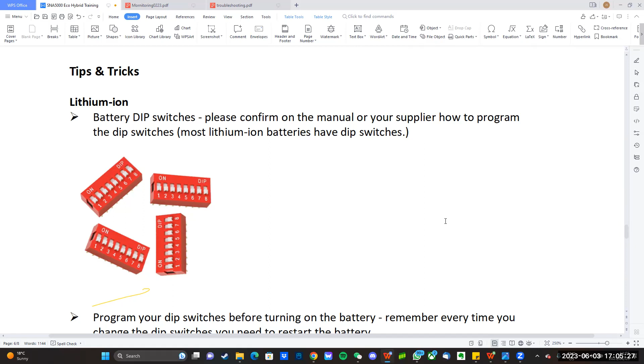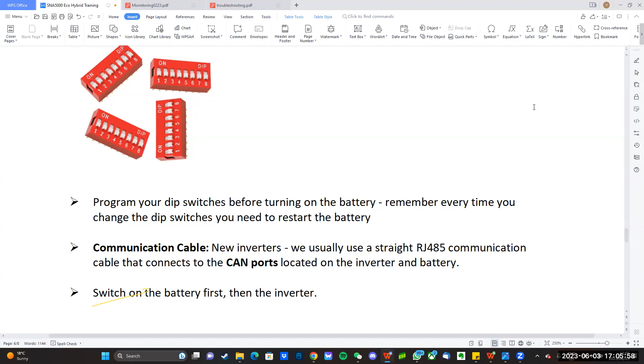Communication cables for your new inverters - like I mentioned, our new inverters have the blue dip switches on them, so they'll most likely use a straight RJ485 communication cable that connects to the CAN ports located on the inverter and battery. Another tip is to switch on the battery first before you switch on the inverter, to avoid any damages.